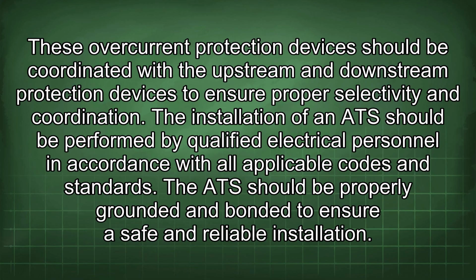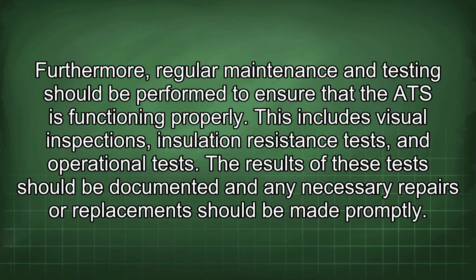The installation of an ATS should be performed by qualified electrical personnel in accordance with all applicable codes and standards. The ATS should be properly grounded and bonded to ensure a safe and reliable installation. Furthermore, regular maintenance and testing should be performed to ensure that the ATS is functioning properly. This includes visual inspections, insulation resistance tests, and operational tests. The results of these tests should be documented, and any necessary repairs or replacements should be made promptly.